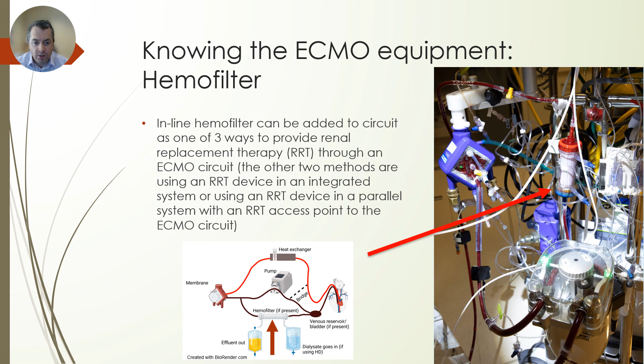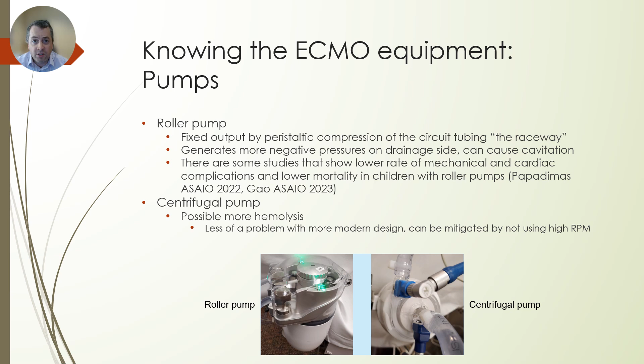Pumps, the things that make the blood go forward. Two main types. A roller pump has a fixed output. As the pump rolls along the tubing, there's a peristaltic compression. It generates more negative pressures on the drainage side than the centrifugal pumps and can cause some cavitation. Some studies show lower rates of mechanical cardiac complications and lower mortality in children with roller pumps. However, those differences are probably less valid with modern centrifugal pumps, which may have originally had more hemolysis, but more modern designs and limiting higher RPMs has limited that.